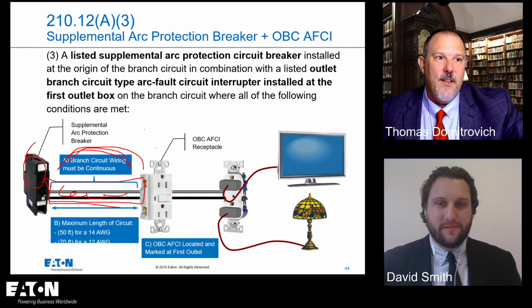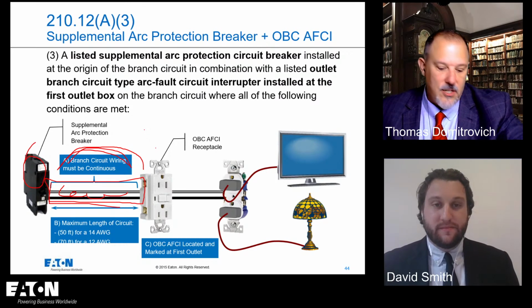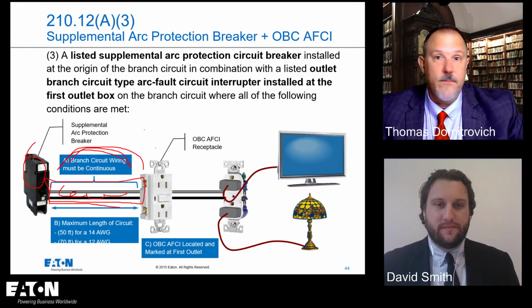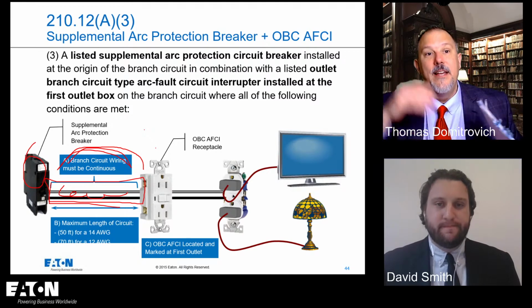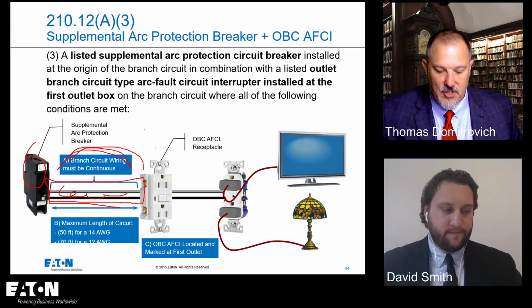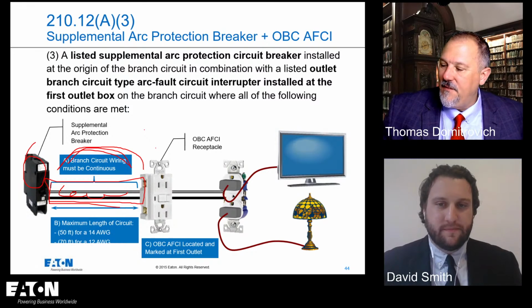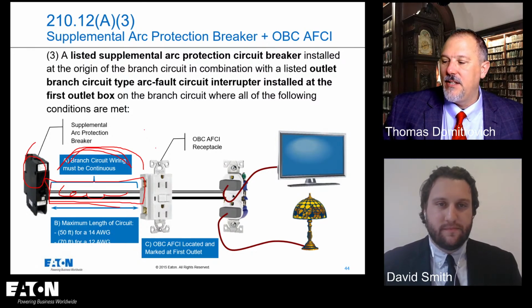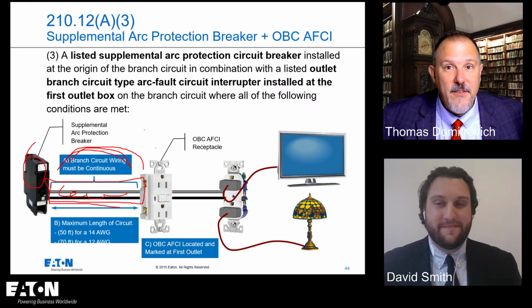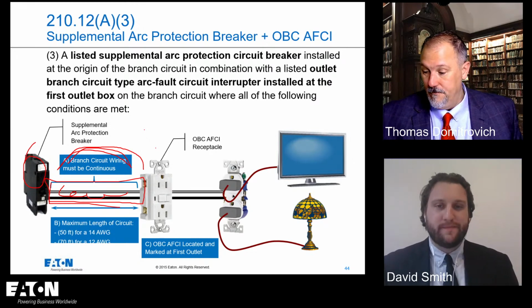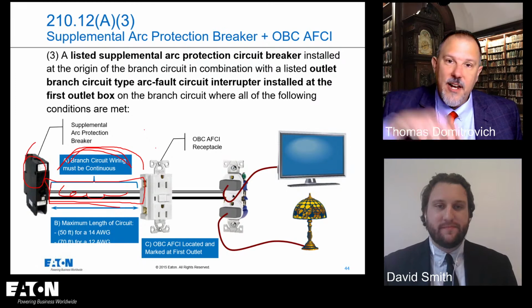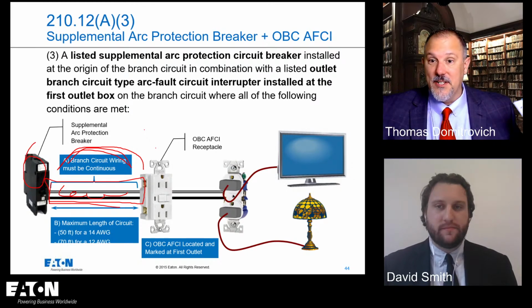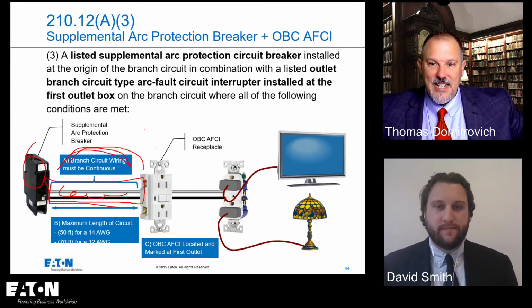So then the other thing was they studied every manufacturer's instantaneous. So first off, we said, look, the fault current values aren't high. So you got to go with 500 amps. Then they said, okay, now let's take a look at the instantaneous pickup on circuit breakers. And they did a nice table of manufacturers A, B, C, and D. They had 15 amp and 20 amp breakers, and they found that circuit breaker positions in the electric panel board, that's fault current, no magnetic trip, greater than 500 amps on a 20 amp circuit breaker, greater than 500 amps. And they found out that not every manufacturer had the same instantaneous pickups. Why? Because it's not required by UL. So the instantaneous pickup values were all over the board.